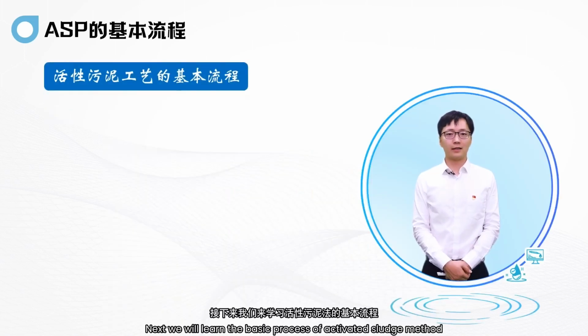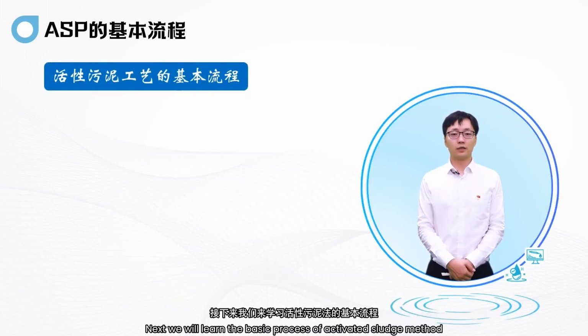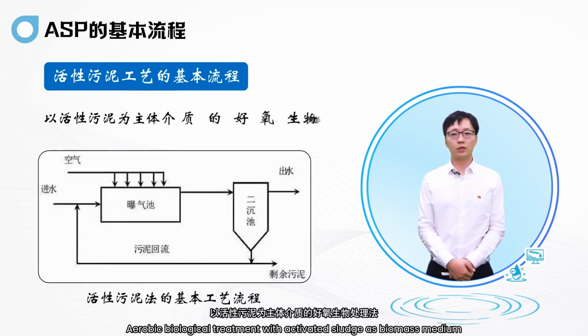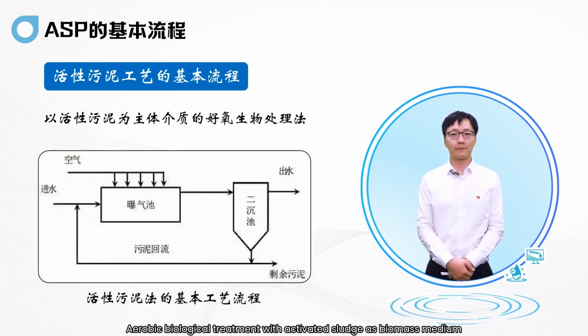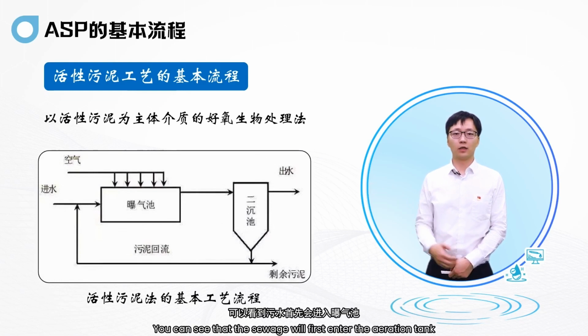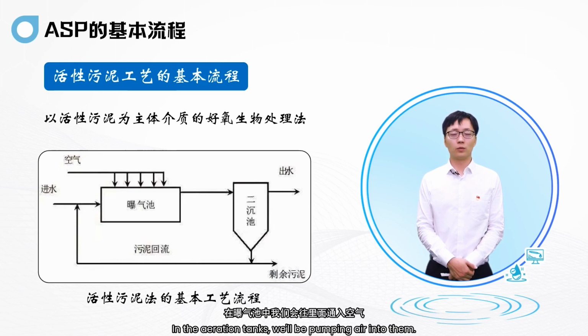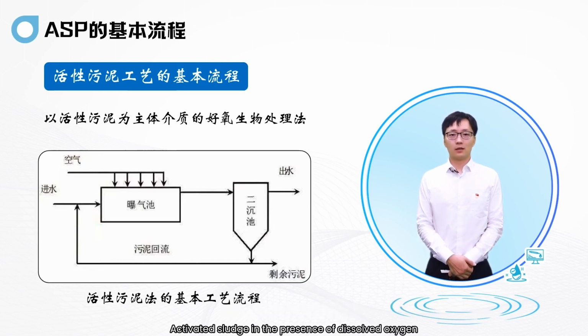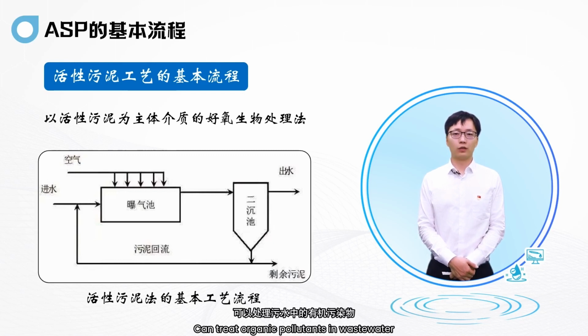Next we will learn the basic process of the activated sludge method, aerobic biological treatment with activated sludge as the biomass medium, as shown in the picture. You can see that the sewage will first enter the aeration tank. In the aeration tank, we pump air into it. Activated sludge, in the presence of dissolved oxygen, can treat organic pollutants in wastewater.